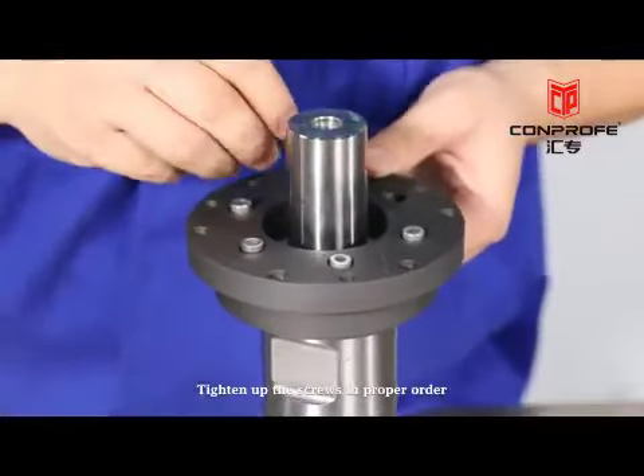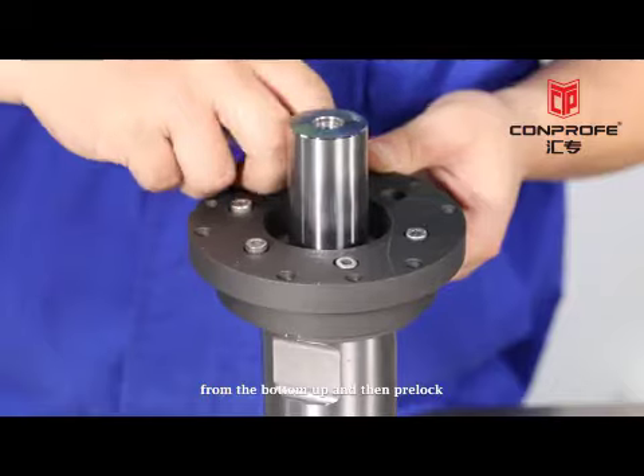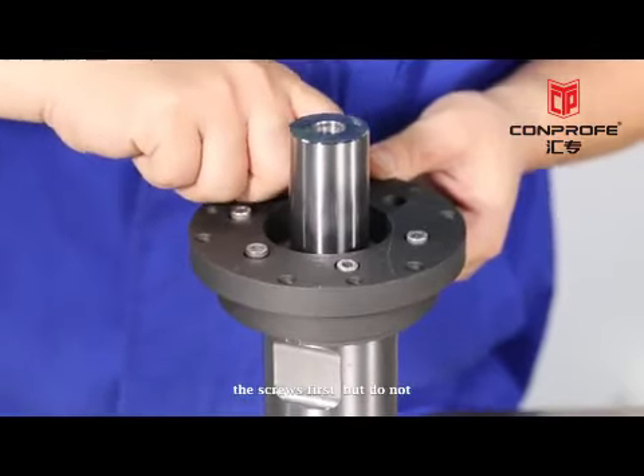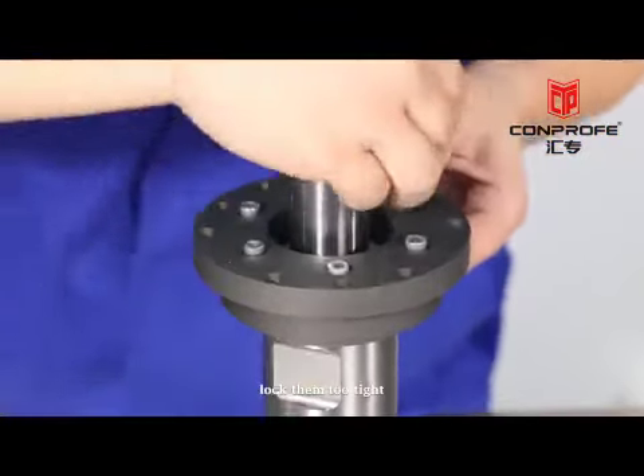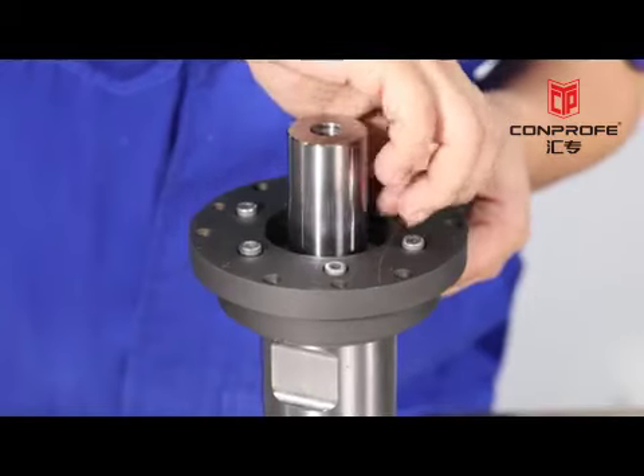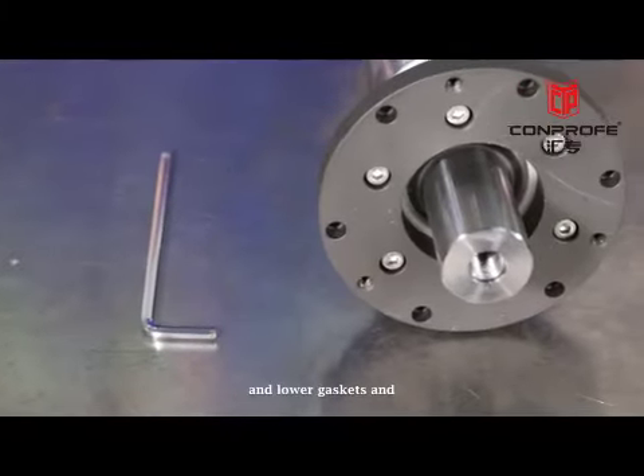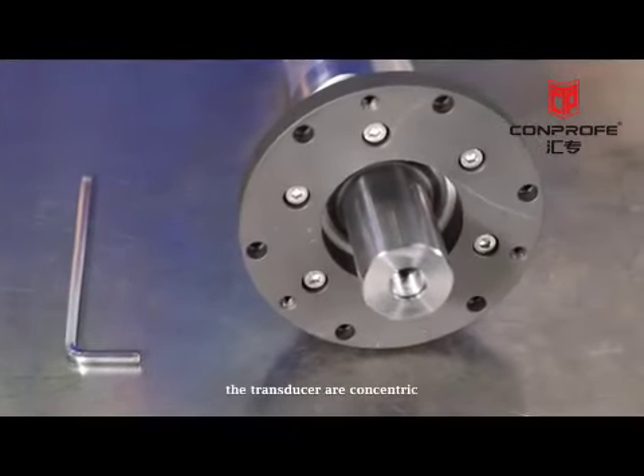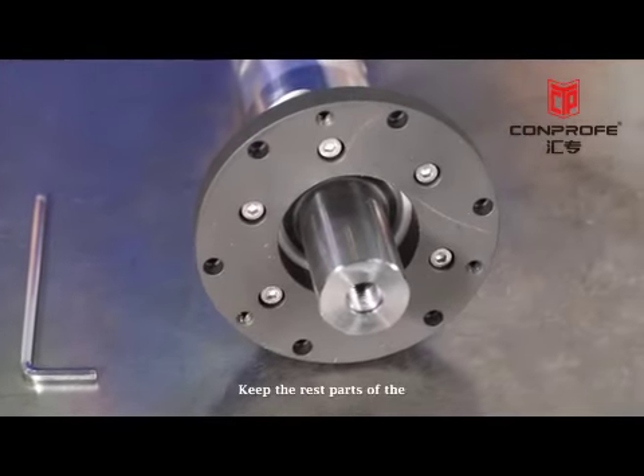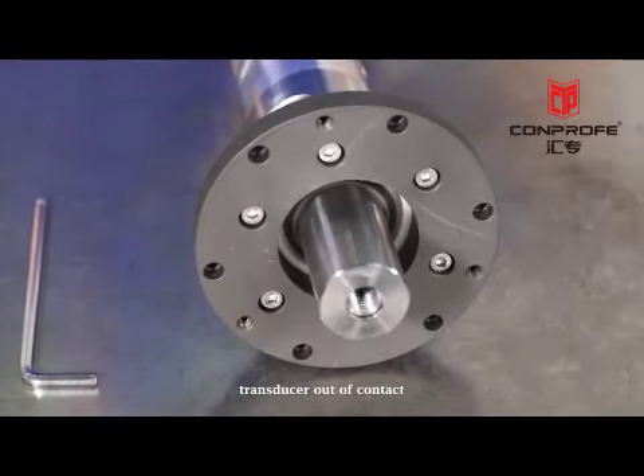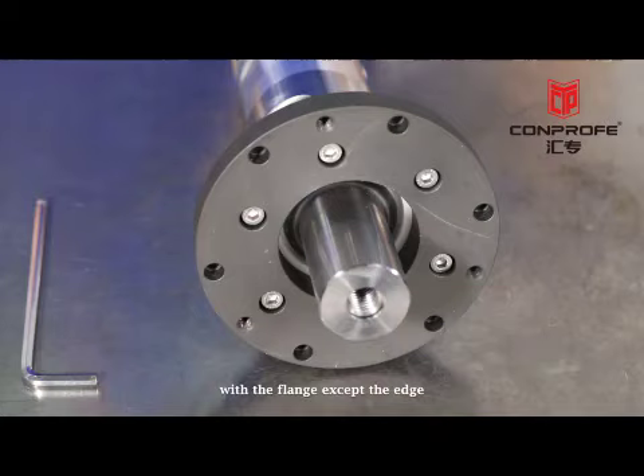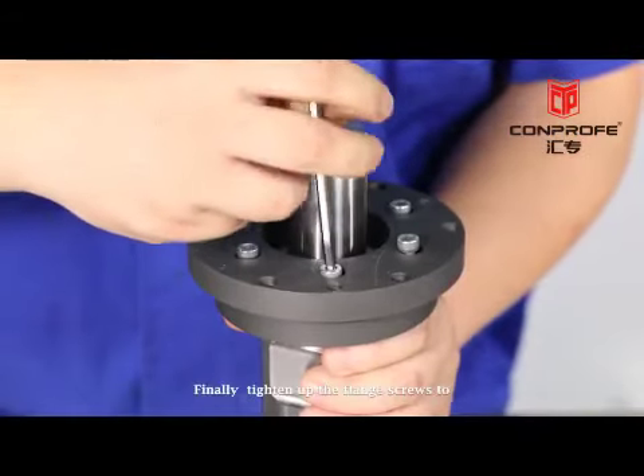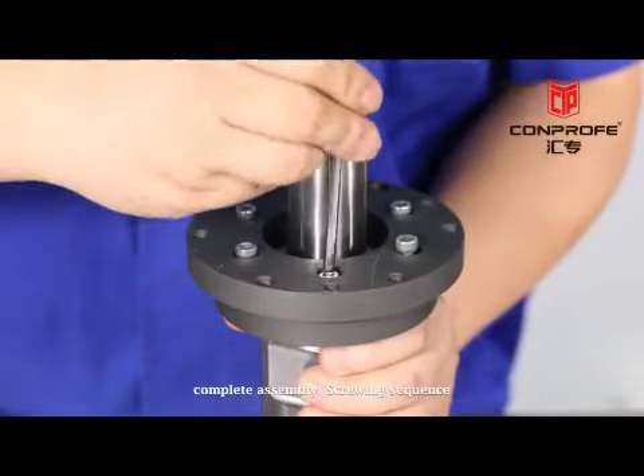Tighten up the screws in proper order from the bottom up and then pre-lock the screws first, but don't lock them too tight. Ensure that the upper and lower gaskets in the transducer are concentric. Keep the rest parts of the transducer out of contact with the flange except the edge. Finally, tighten up the flange screws to completely assemble.